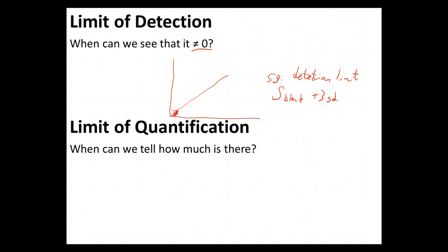Maybe it's a Spec 20, or maybe it's the analytical balance. You're standing there looking at it, you've zeroed it out. You're watching it. Watch it for about 2 minutes. Do you ever see the number leave zero? Sure, almost definitely. And that means there's just a tiny bit of randomness, and it's causing it to occasionally flicker.